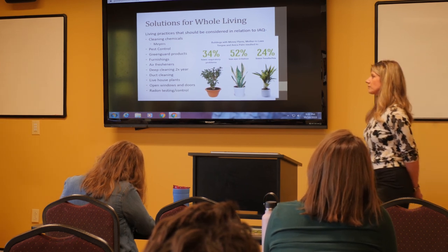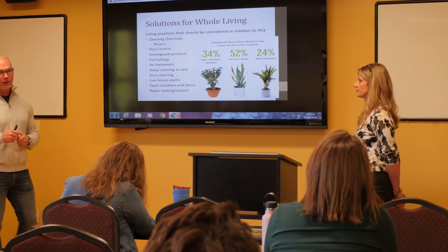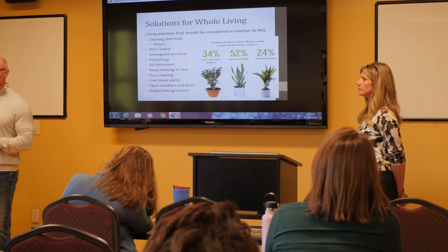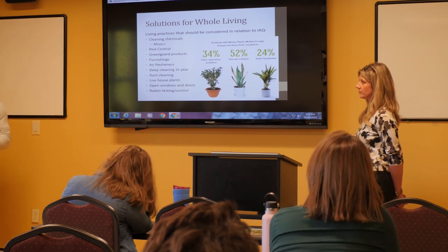So we get a reliable reading. We'll test it. If it comes in over four, then that is considered dangerous. And we will have our radon mitigator come in and put a vent or a fan in the vent to make it an active system.